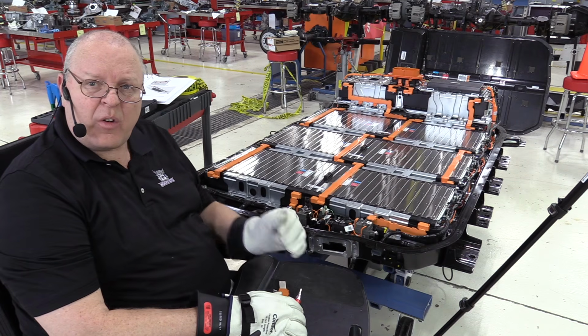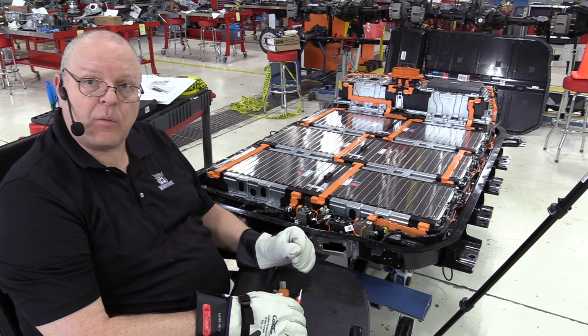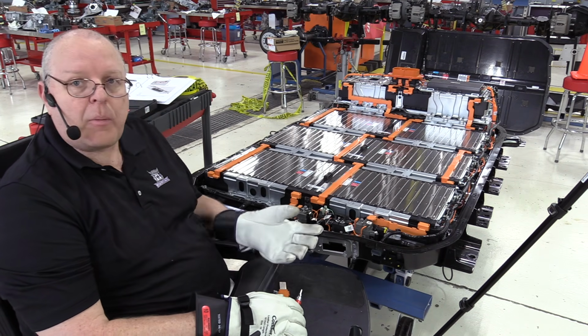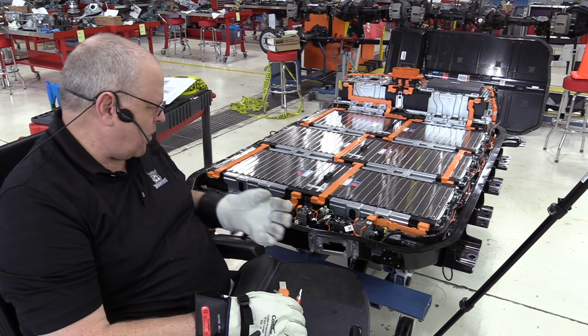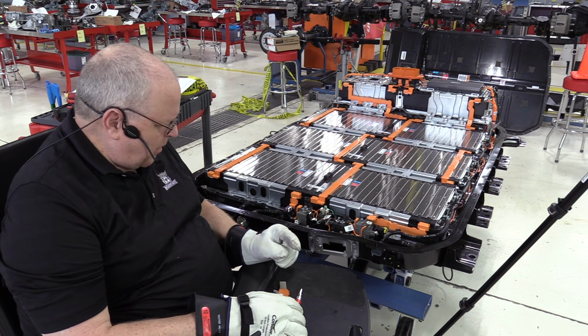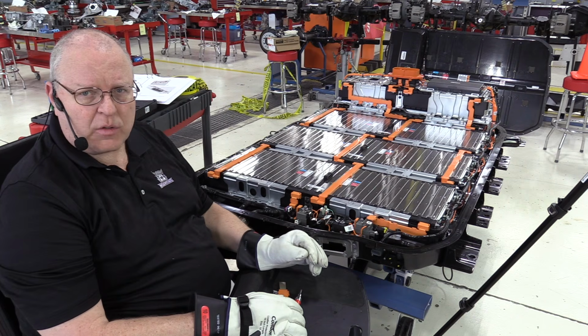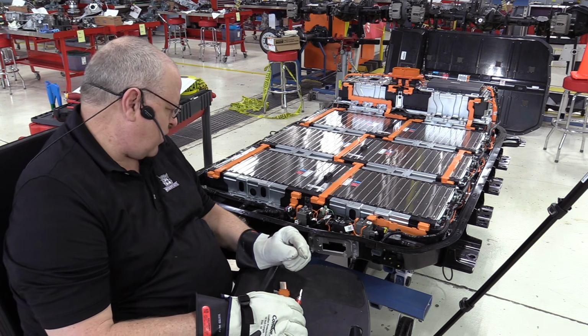So all 350.4 volts, which is the nominal voltage. It'll be higher than that when it's fully charged, lower than that when it's discharged. But that's at 3.65 volts per cell, the nominal voltage.